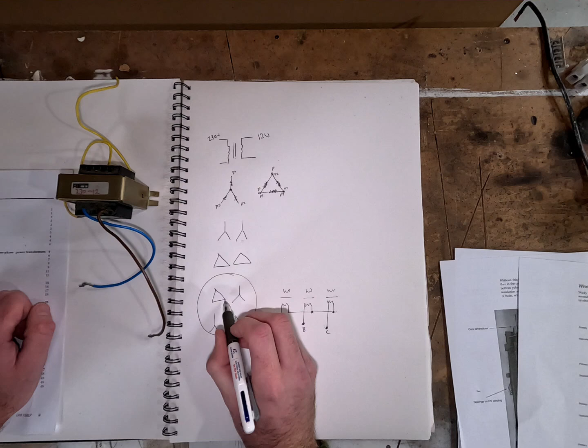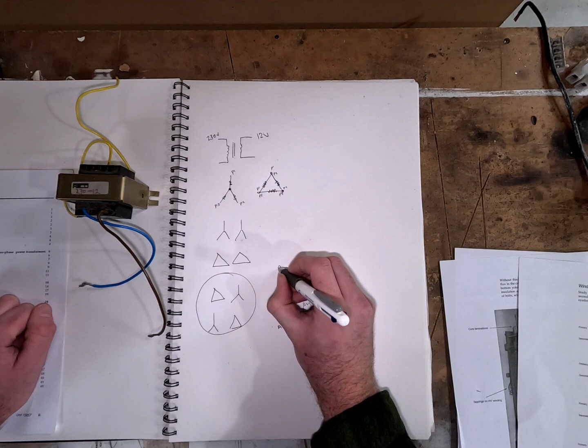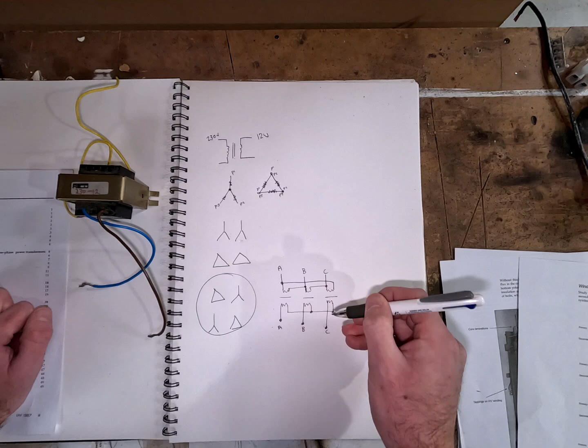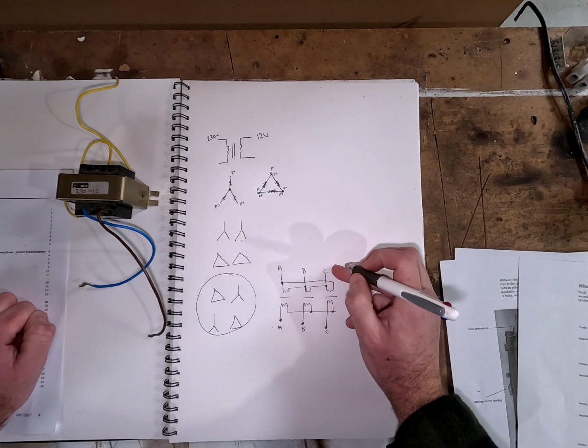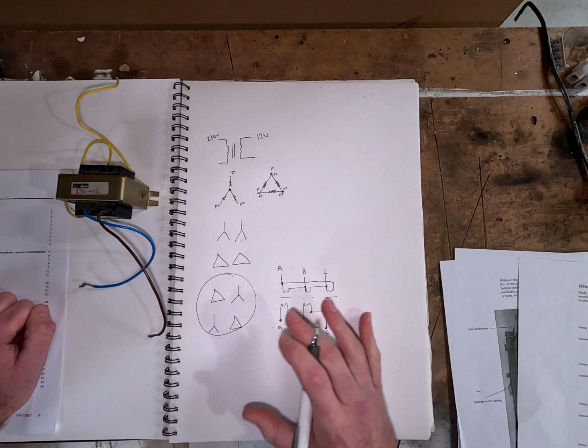Then you just need to connect your three phases to the end points of the coils, so we can call them 1, 2, and 3, and that's A, B, and C, like that. So this is a delta, and that's a star. And obviously if you have it the other way around, then you just make this the primary and this the secondary. So that's the basics of the wiring of a three-phase transformer.